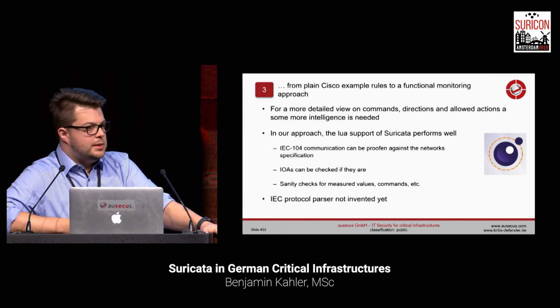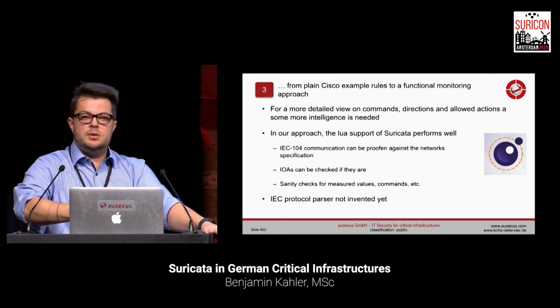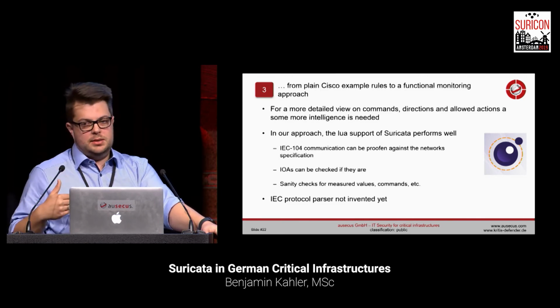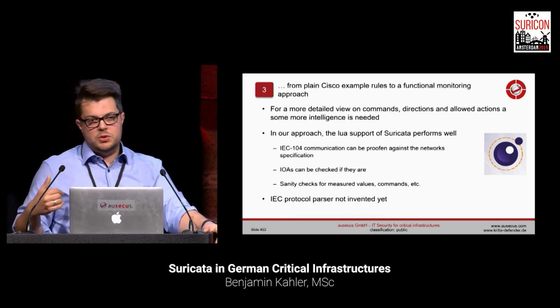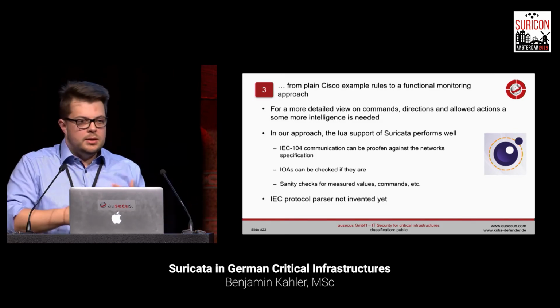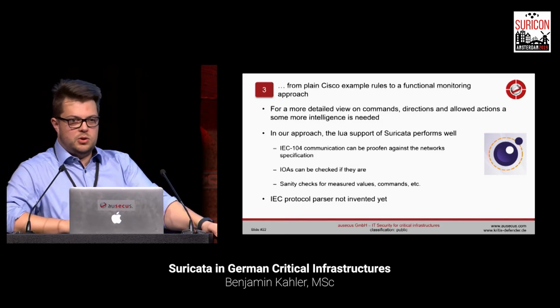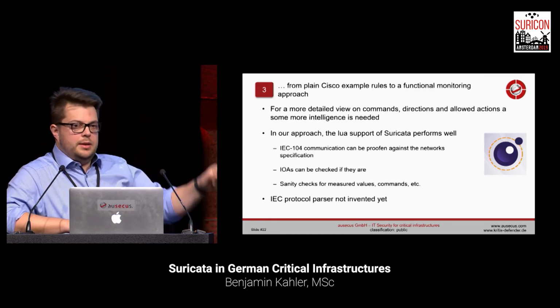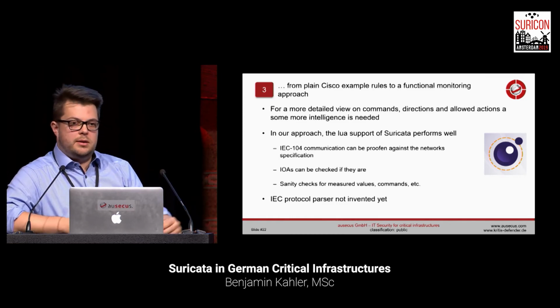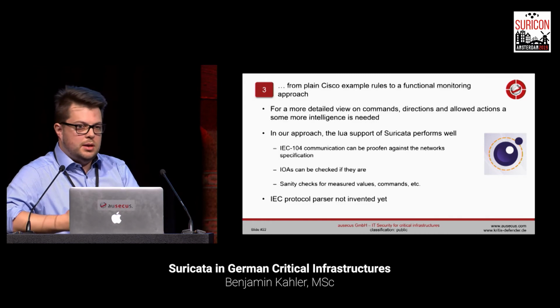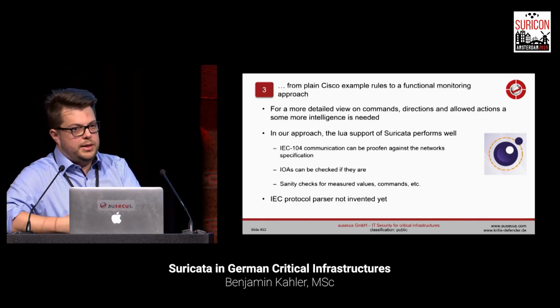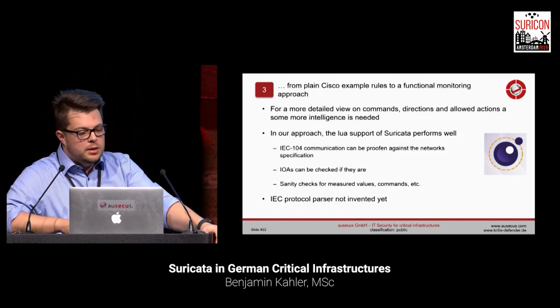We can check if this single command is in use against the network specification. Some SCADA systems only use single commands, they don't use the feature of double commands. So if the SCADA system doesn't use the double command feature and we've seen some double commands in the network, then we can trigger an alarm because that's not a normal packet, that's a packet outside the specification.